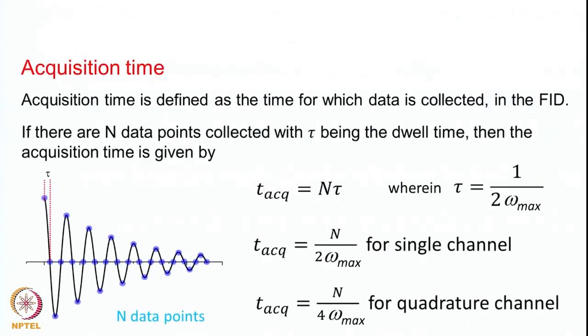The next parameter is the acquisition time — how much data you collect. Acquisition time is defined as the time for which data is collected in the FID. The FID starts here and you collect the data all the way until the signal decays. Beyond that, there will be mostly noise. You do not want to collect noise — you are limited by the relaxation of the signals. By about three times the transverse relaxation time, the signal would have decayed almost to zero. If you collect any data beyond that you are basically collecting noise. The total time from start to end is called the acquisition time.